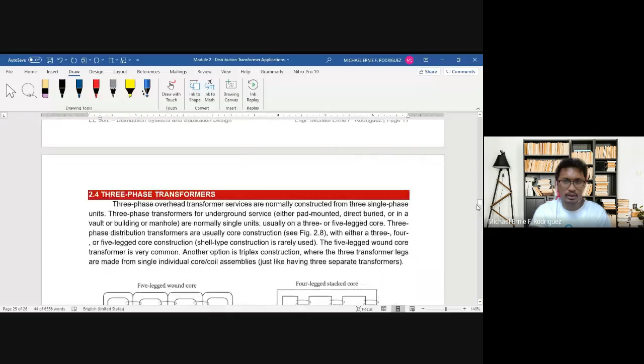In three-phase connection, you have banking. The kVA rating of your three-phase bank, just add the total. So if you have a bank of three transformers, let's say this is 25, let's make it so we can add. So you have three transformers at 37.5 kVA, just add all of that, so you have 112.5 kVA. That is the kVA rating of your three-phase bank. Just add all of them. So if you have three at 167 kVA each, that is 500 kVA.